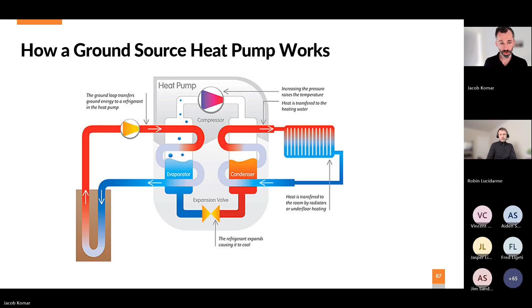A ground source heat pump, we're using the stable earth temperature and water, which means we can do it much more efficiently. And that's why in heating, we don't care if it's -40 outside. As long as we size the ground properly, we have stable earth temperature. And of course, the cool thing about heat pumps is we're not creating heat, we're moving it. So if we add 1 unit of heat into the compressor, we're moving 3 units of heat from the ground, which means for 1 input, we get 4 out. That's why our efficiency can be 400% on average with a ground source heat pump.